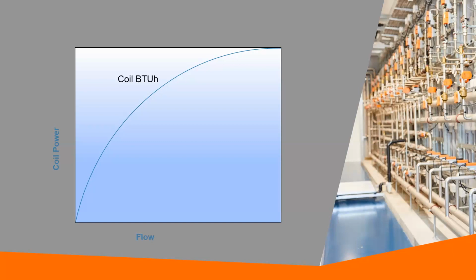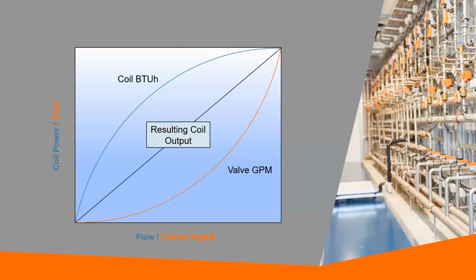As you can imagine, this nonlinear shape is basically difficult to do any control with. So what we have is a control valve with an opposing shape. Here the axes are different. The x-axis is the valve opening or control signal, while the y-axis is the flow through the valve. The valve by design opens very slowly to counteract the fast-acting nature of a coil at low flows. Okay, so if you take a look at this, what it does is it gives you a linear output that results. And if you chart this, about 20 to 25% of the flow is about 50% of your heat transfer in that linear resulting output.